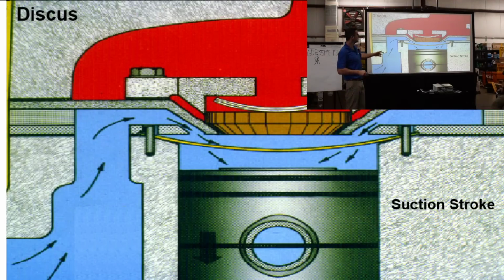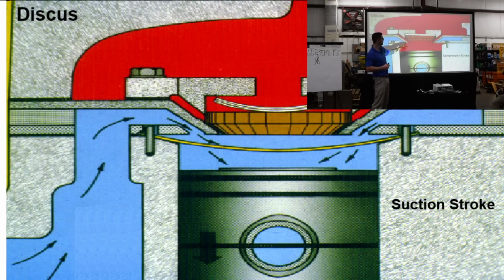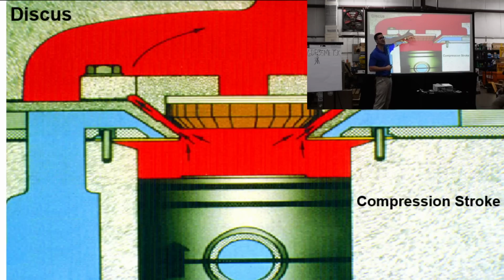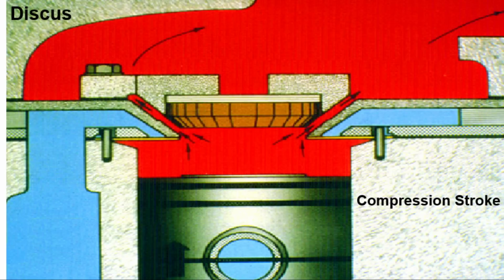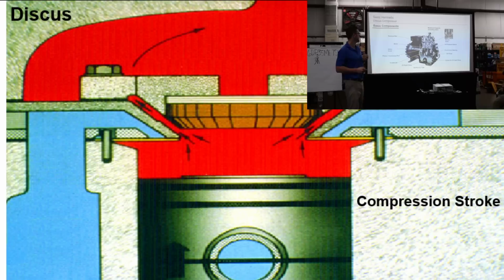This is how it works. This is your suction. As that piston comes down, it pulls down your suction on your suction stroke, pulls the valve open, and then when it compresses, it closes your suction valve here and pushes up the disc. Pushes that up and you discharge out. See how you notice there's virtually no volumetric efficiency loss. Okay?